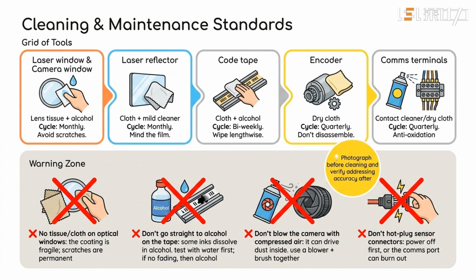Cleaning the addressing system looks simple, but the details matter. Use lens tissue and absolute alcohol on the laser and camera windows, and a lint-free cloth on the reflector and tape. A few don'ts to remember. 1. Never wipe optical windows with an ordinary cloth. 2. Don't go straight to alcohol on the code tape. Some inks dissolve in it, so test with water first and only use alcohol if there's no fading. 3. Don't blow the camera with compressed air, which drives dust inside. 4. Never hot plug the sensor connectors. And 1 rule: photograph before cleaning, and verify accuracy after.